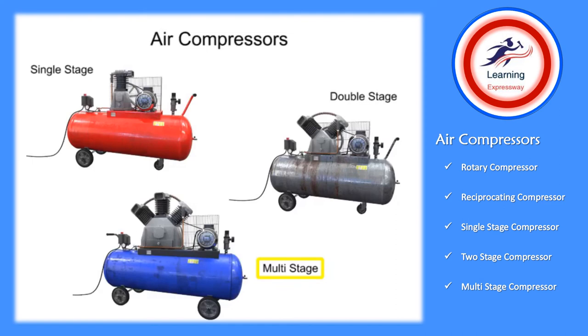On these larger compressors, cooling may take place by circulating water instead of air. To reach a pressure of 2,500 psi, as many as 6 or 7 stages may be needed with cooling between each stage. Their versatility makes compressors one of the primary components in air production.